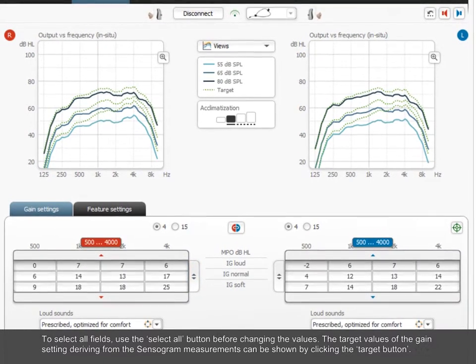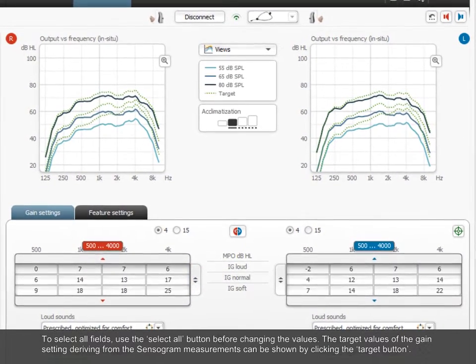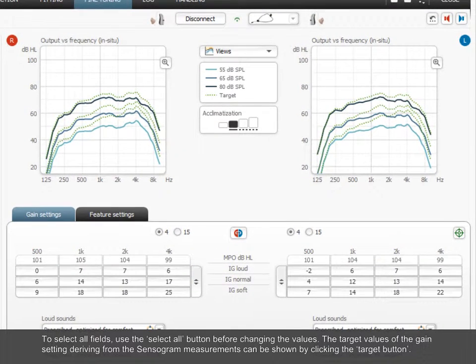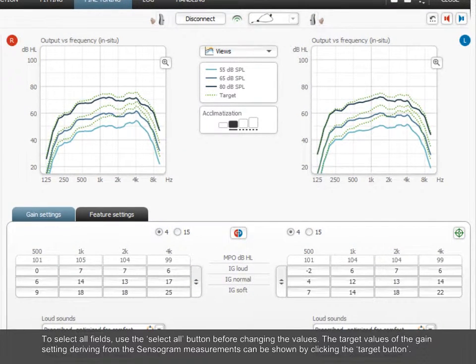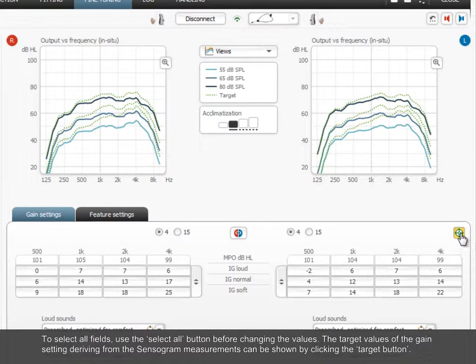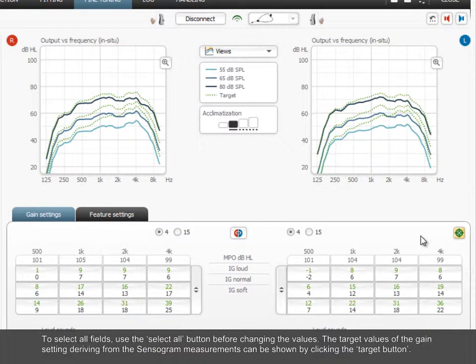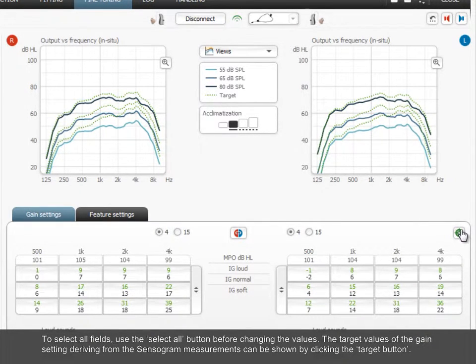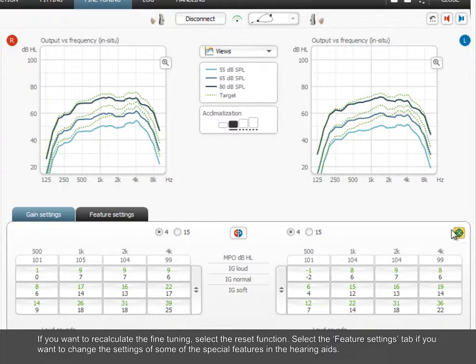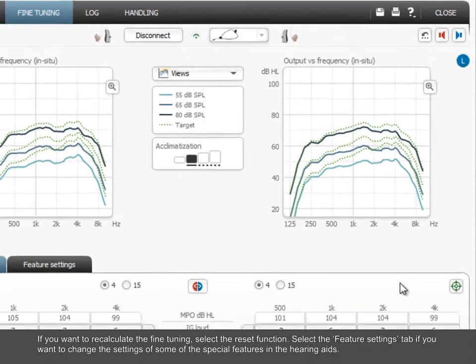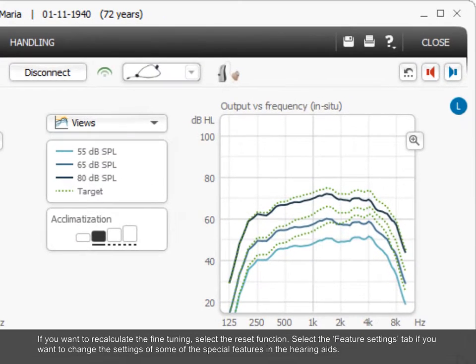The target values of the gain setting deriving from the Sensogram measurements can be shown by clicking the Target button. If you want to recalculate the fine-tuning, select the Reset function.